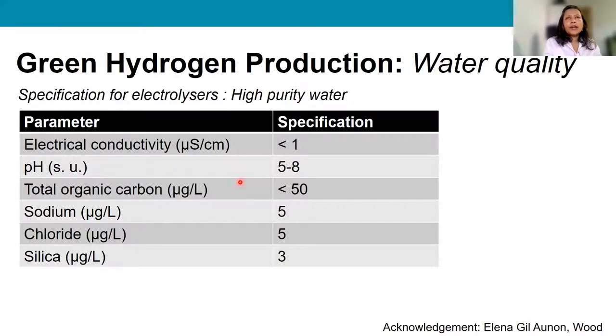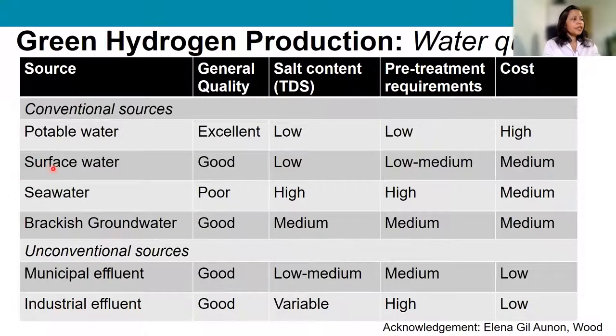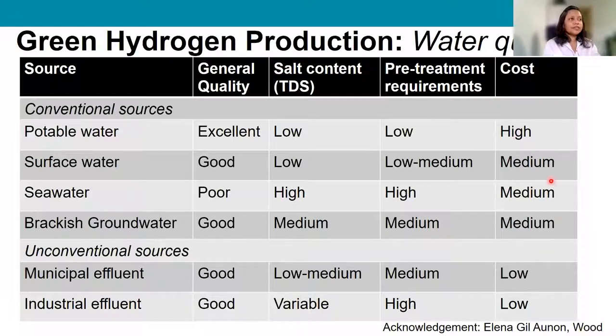When considering seawater and wastewater as sources, water quality must meet specific requirements for the electrolyzers in terms of conductivity, pH, total organic carbon, salt content, and silica. Different water sources may require different treatment, and there is a cost associated with each source that needs to be considered.